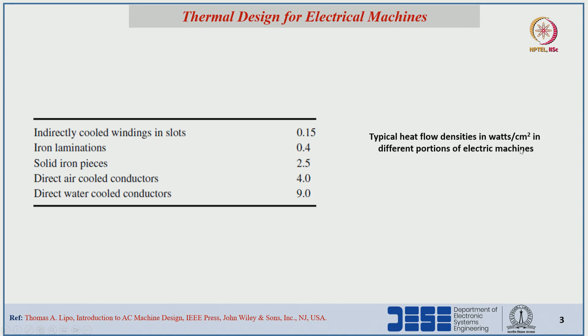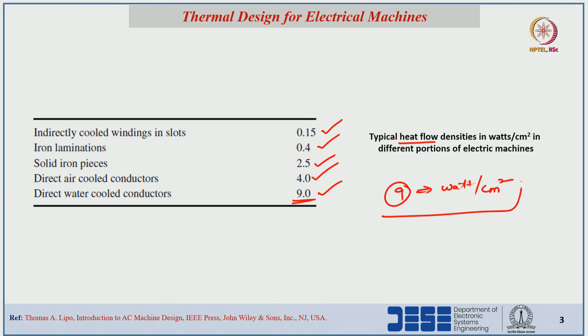The typical heat flow densities in watt per centimeter squared in different portions of electrical machines are: indirectly cooled windings in slots — 0.15, iron laminations — 0.4, solid iron pieces — 2.5, direct air-cooled conductors — 4.0, and water-cooled machines — 9. So for high power density machines, we have to design the thermal system with direct water cooling or liquid cooling systems.